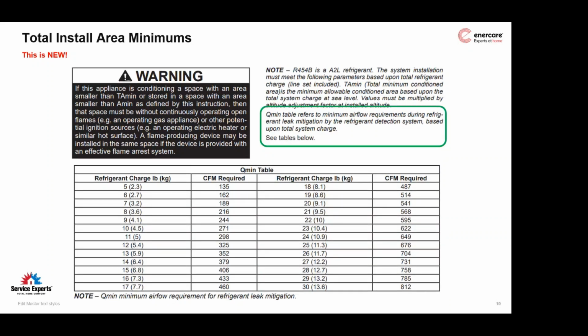There's also a note here that you can see highlighted, called Q minimum table. Basically it refers to the fact that there's also a minimum CFM required during dilution. When I say that, what I mean is in the event there happens to be a refrigerant leak, maybe one of the lines has a small leak, or the coil has a small leak in it, or one of the elbows, one of the manufacturer's joints has a small leak in it, a couple years down the road.